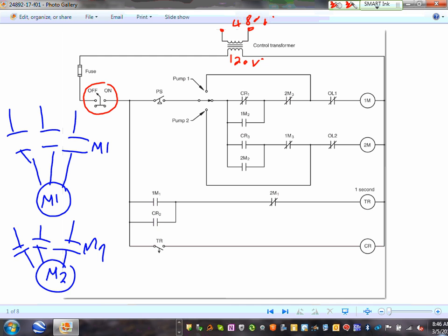If I want pump 1 to work, you click this one and put it in pump 1. This will energize, these contacts will close, and now pump 1 is running. If I put it in pump 2, you turn it to pump 2, pump 2 is energized, the contacts close, and pump 2 is running. So you have a selector switch — pump 1, pump 2, or auto. Pump 1 and pump 2 are manual; you can force one of them to work manually.